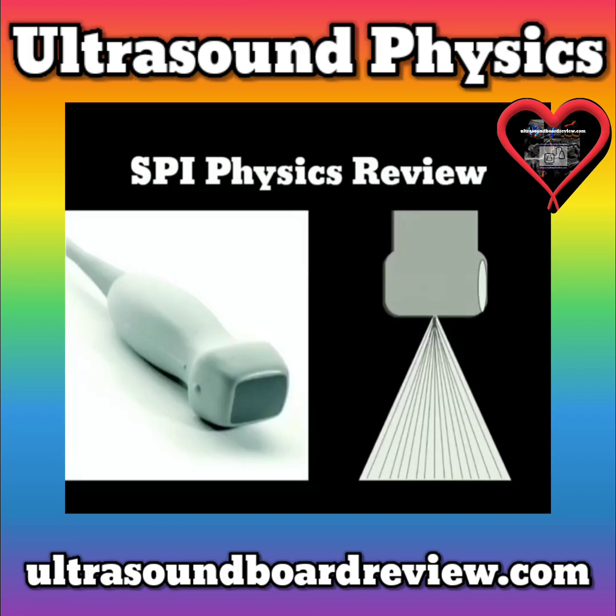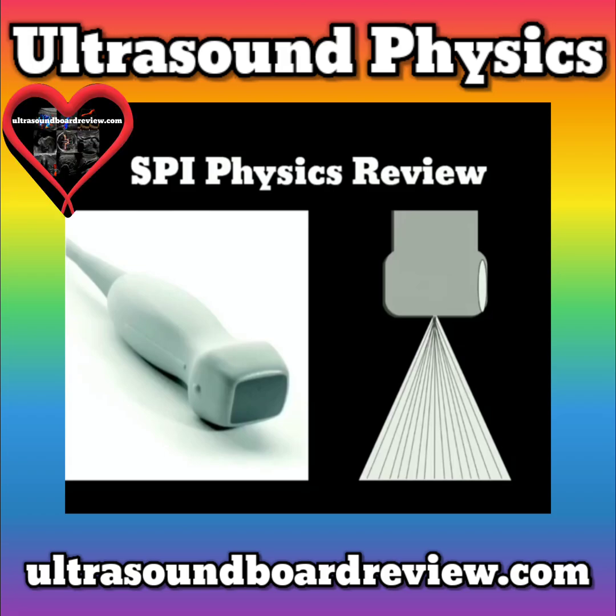The phased array starts from a very narrow point and splays very widely. This gives you the worst resolution out of all three types of probes. However, this also gives you the smallest footprint in order to image through a very narrow space. And that's why this is used as a cardiac probe for echocardiography, because you can get in between the ribs and in between lung spaces to try and get to the heart.